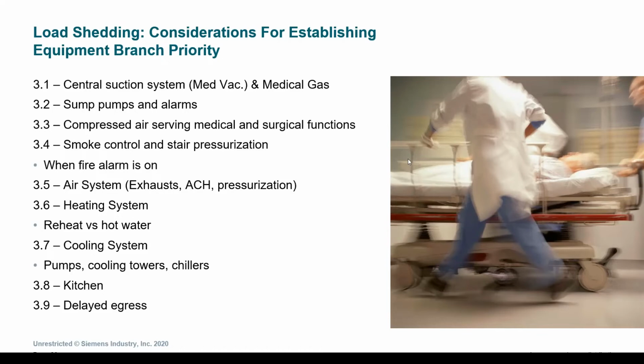The mechanical system, it's important to consider holistic prioritization of the system. So for instance, if you have an air handler, it is important that the cooling tower, chiller, and pump associated with maintaining that, along with the control circuits, are also identified as a higher priority, equal, to make sure that operation for that space could be maintained. From there, it would also include the heating system, and then cooling system, if there's any redundancy, followed finally by the kitchen and any delayed egress.